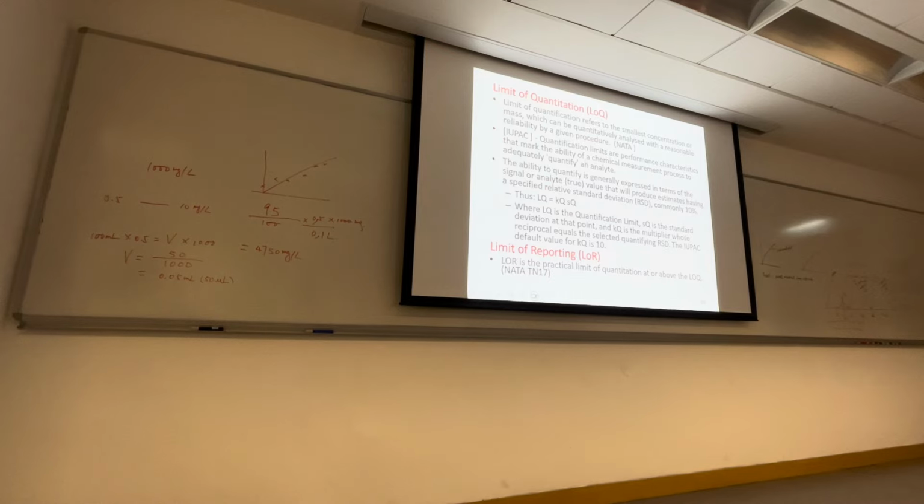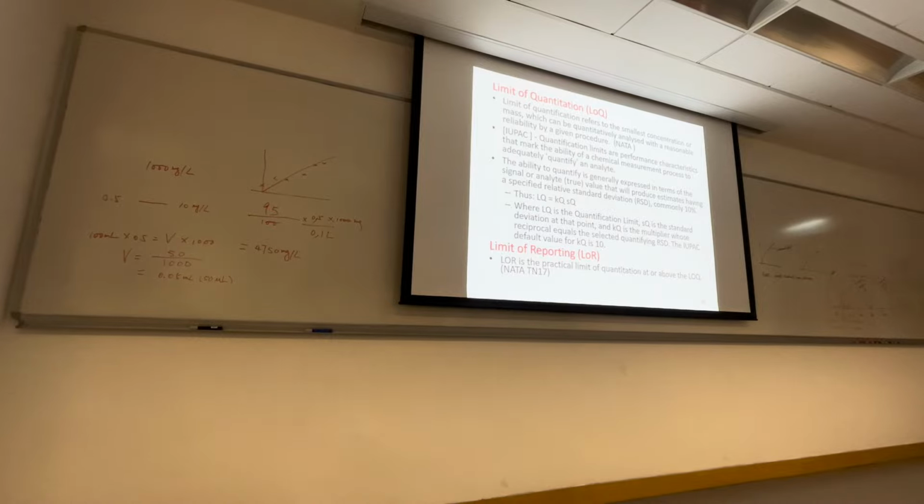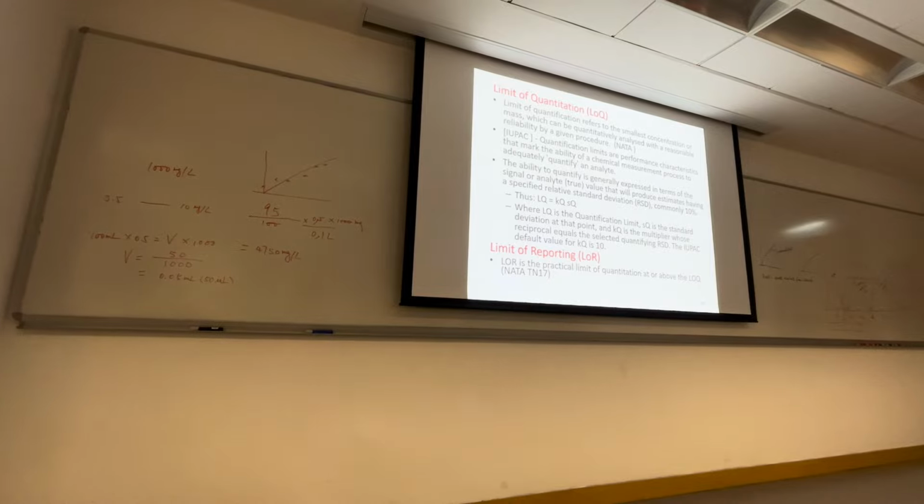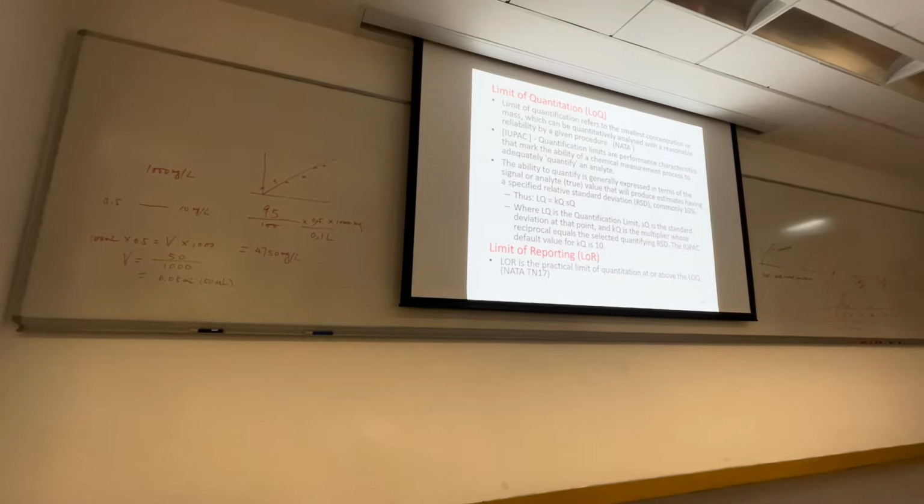Then LOQ is simple. That means the smallest concentration that can be quantified with reasonable uncertainty or reliability. That means we are quite certain of the quantified result. And this is the limit of quantification. For the limit of detection, we just say that we are capable of differentiating the signal from the background. But the quantified result is really uncertain. In Hong Kong, we do not allow reporting anything at LOD. So that will give you the limit of reporting.